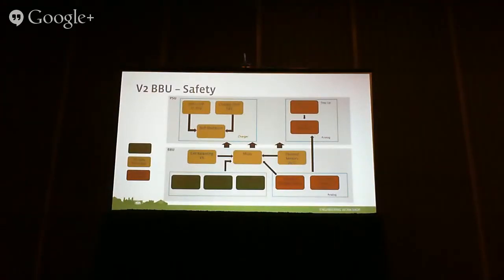Primary protection is what the BBU can offer on its own, and it can communicate out—that's the micro it's got. It's monitoring variables, it's got thermal sensors, it's got cell balancing ensuring everything is within range. It can send signals to the power supply saying stop charging me, or stop discharging me, stop using me. Those are usually digital, translated by an analog signal between the power supply and BBU.